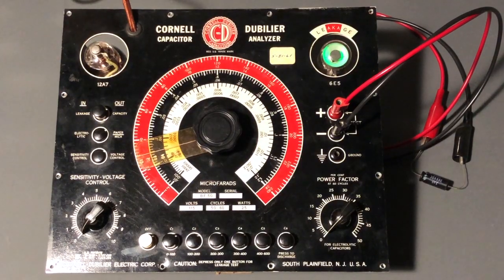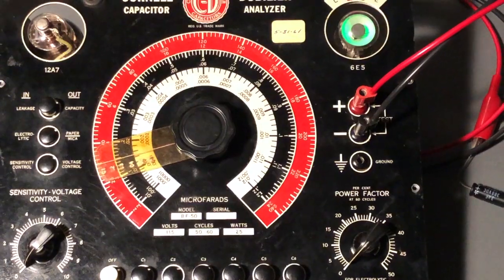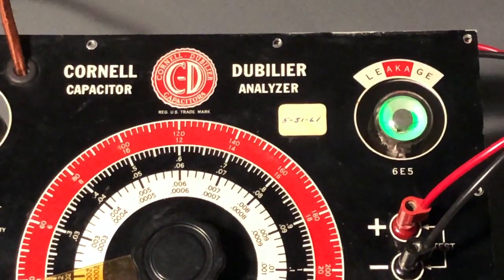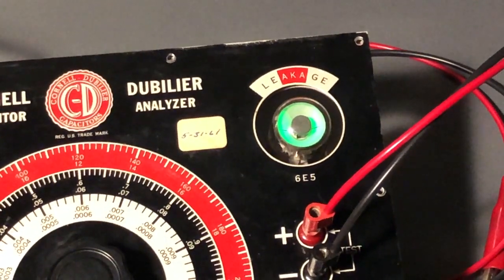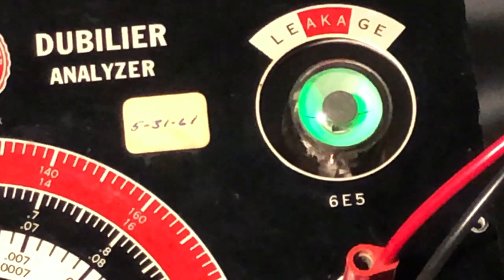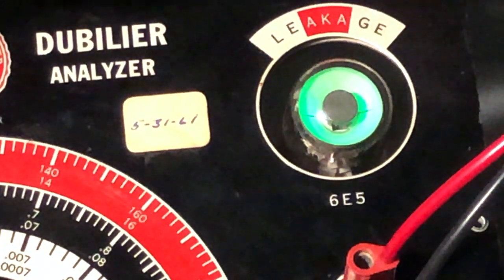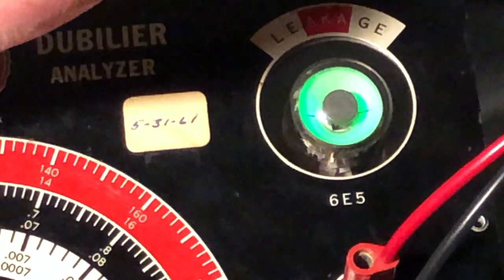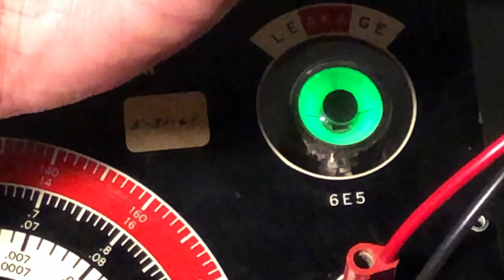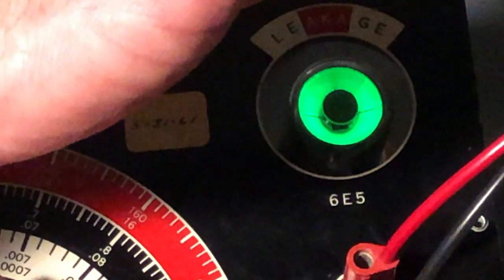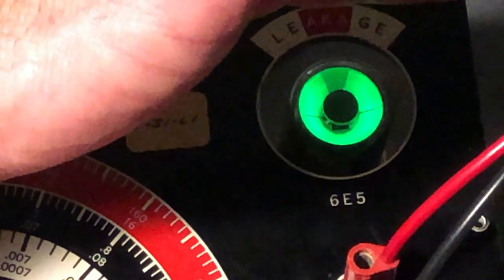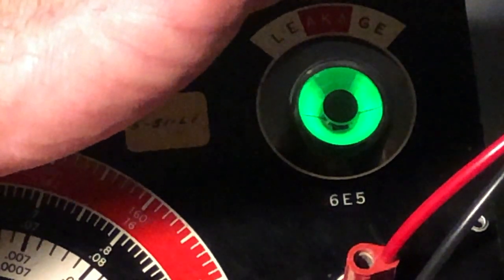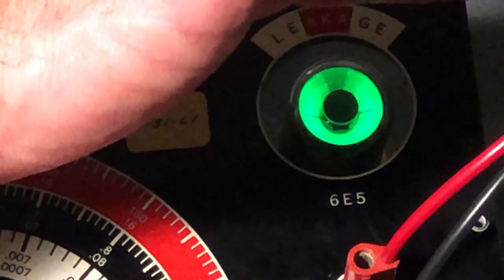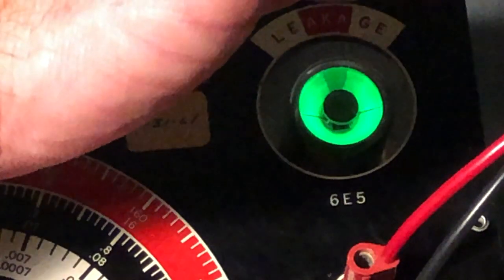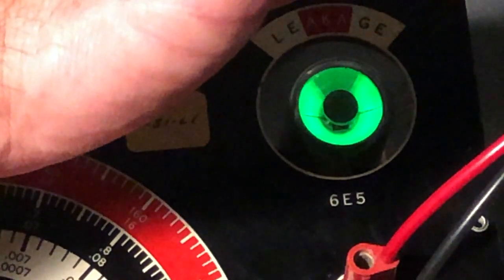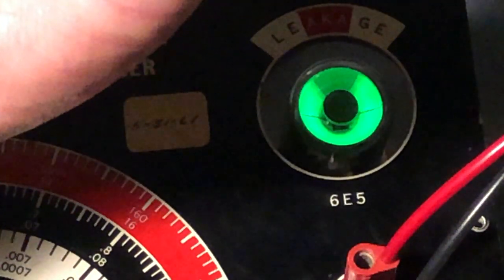So let me zoom in one more time and do the test again, and I'll just zoom in closer on the eye tube so that you can see how that looks. So with the camera zoomed in, let me do the test. I'm going to shield this from the light overhead here. I have most of the lights turned off, but there's just a lot of glare on that tube. There we go, like that. Okay, so I'm increasing the control. You can see the tube is indicating, the eye is indicating a wider opening. And then as I'm still increasing the control, you can see the eye is now closing. So I'll back up. Now I'm lowering the control back down, looking for that maximum opening right there.